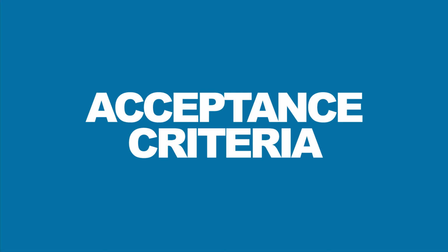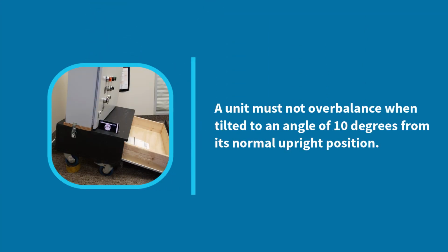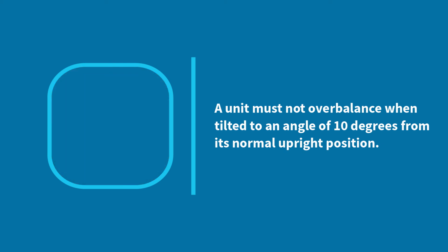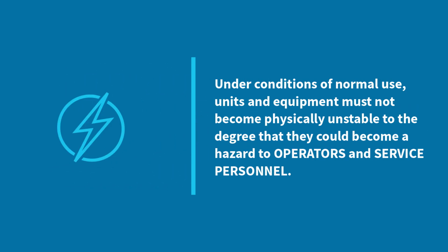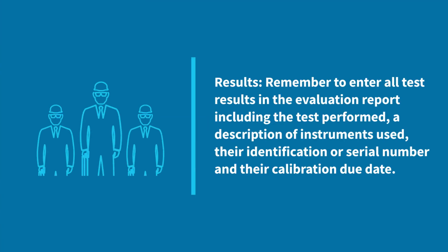Acceptance criteria. A unit must not overbalance when tilted to an angle of 10 degrees from its normal upright position. Under conditions of normal use, units and equipment must not become physically unstable to the degree that they could become a hazard to operators and service personnel. Results. Remember to enter all test results in the evaluation report, including the test performed, a description of instruments used, their identification or serial number, and their calibration due dates.